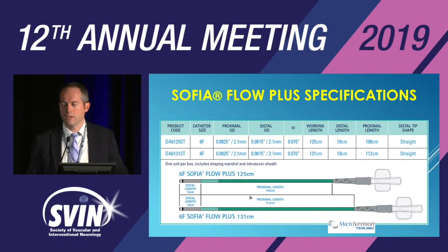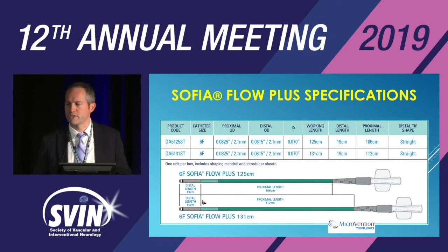The tips are identical, with a 19 centimeter soft tip at the end of the catheters that does the magic and goes around the tortuous vessels. The inner diameter is 0.070, the outer diameter is around 2.1 millimeters, and both have straight tips, so there's no bend at the end.